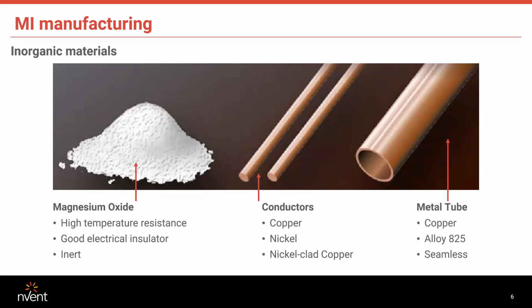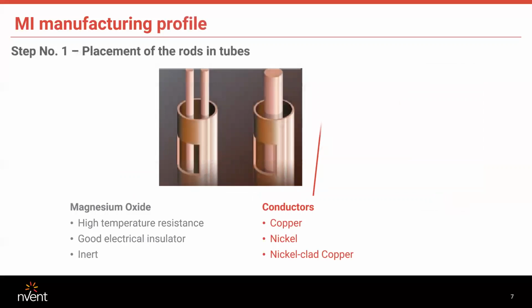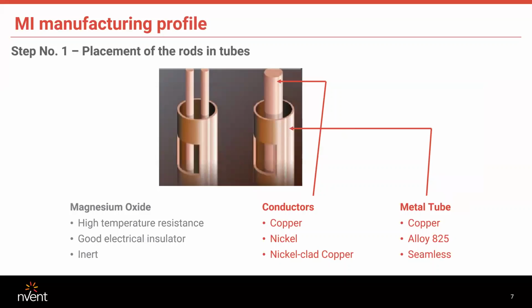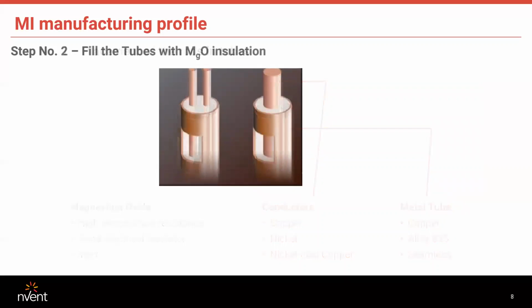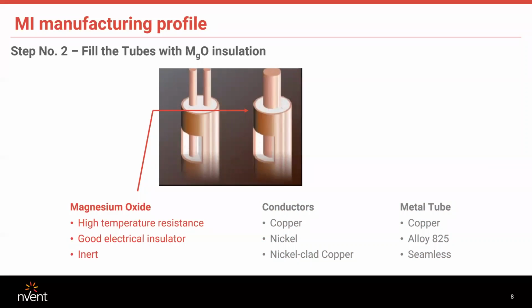When we manufacture the cable, we start out with that magnesium oxide, copper tubing that's about 2 inches in diameter and 30 feet long, and then copper conductors, which are at this moment copper bars that are about 30 feet long, anywhere from 1 up to 7 depending on how many conductors we're working with. We take those copper bars and the copper tubes, and we place them vertically. What we then do is pack those tubes that are about 30 feet long with magnesium oxide.